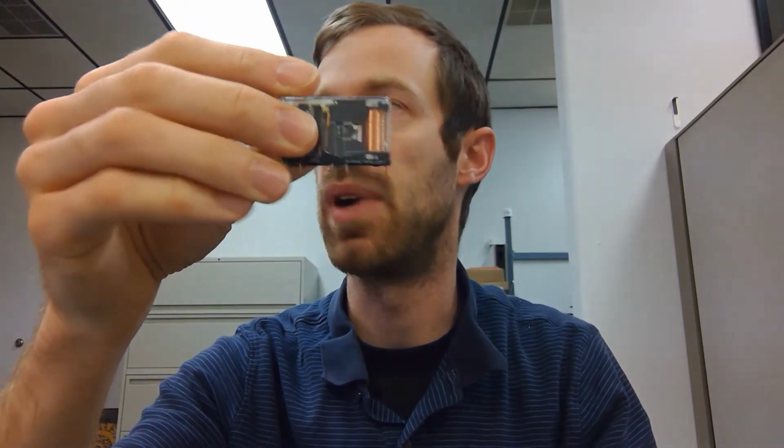So be very careful that you've used the properly rated coil. This one's a little tougher. Got to read the fine print because I don't have tape wrapped around that to just say, oh, it's 24 volts or 120 volts. Now if I use too little voltage, like this one should be, let's see, yeah, 5 volt DC. Focus is tough. 5 volt DC. So that means that the coil is going to be activated with 5 volts.